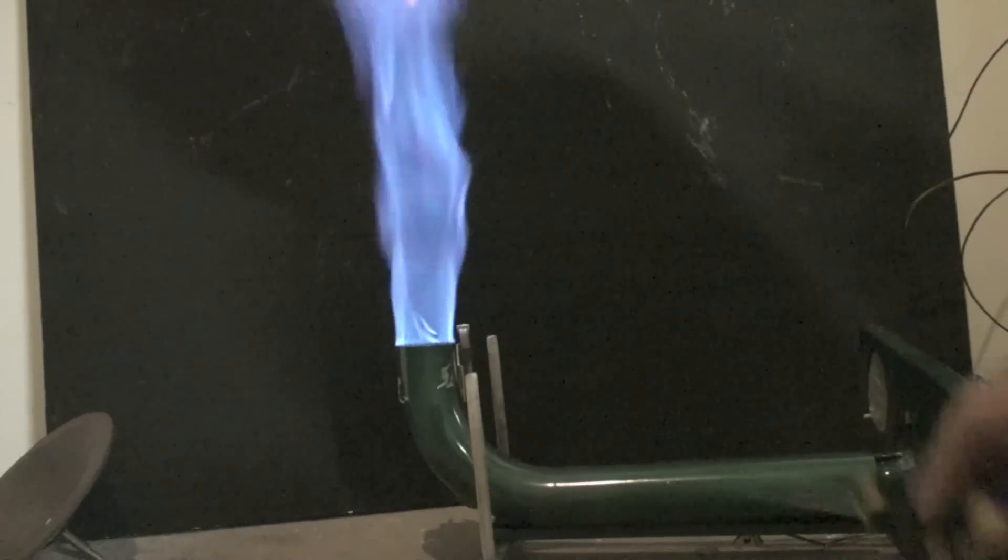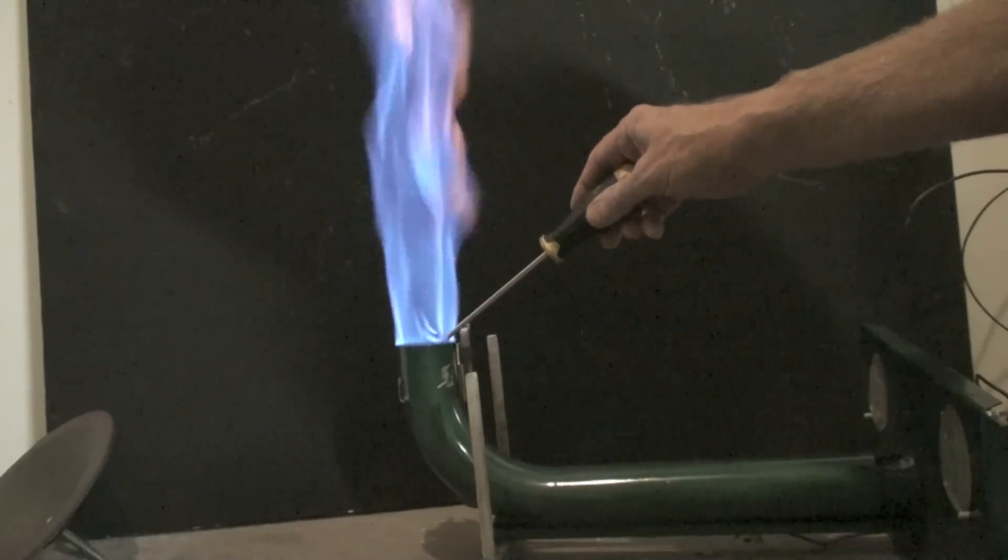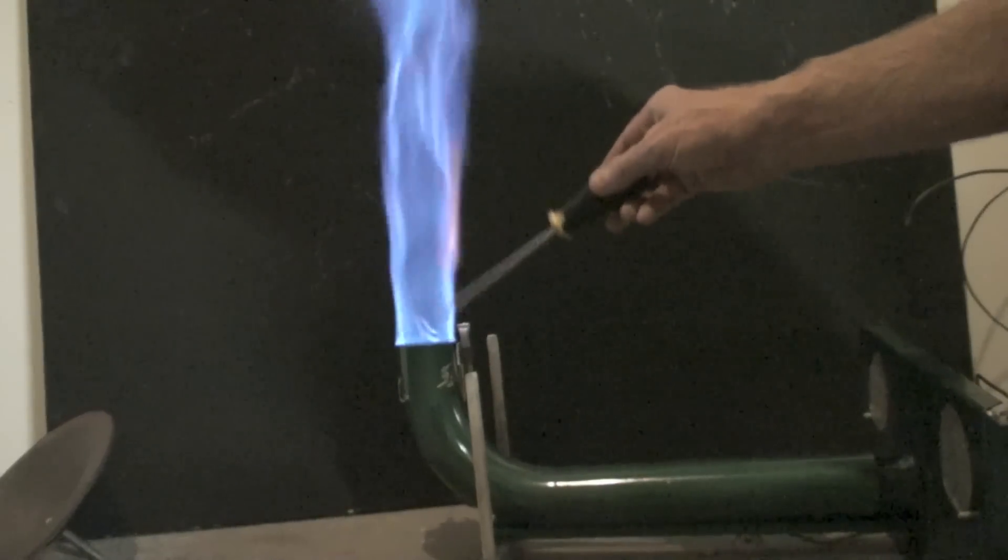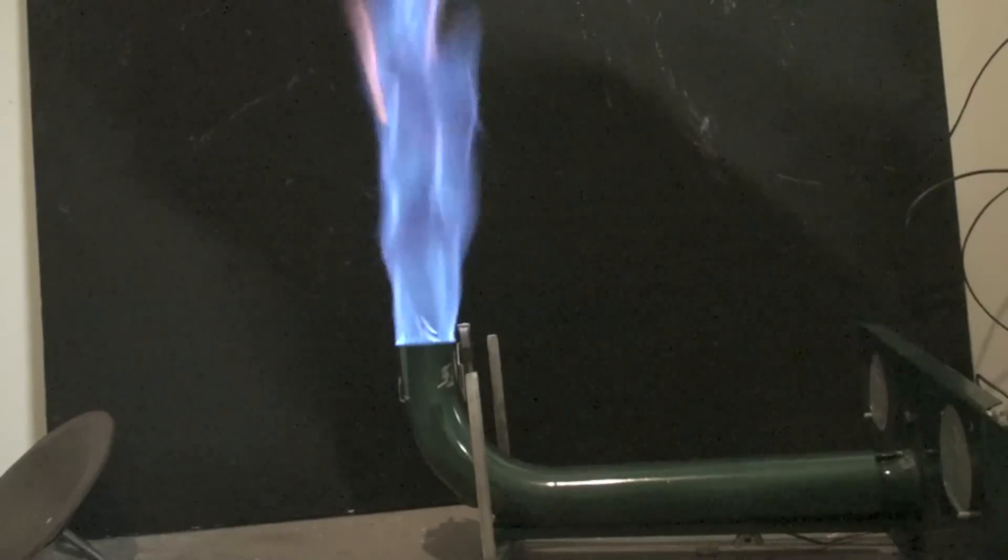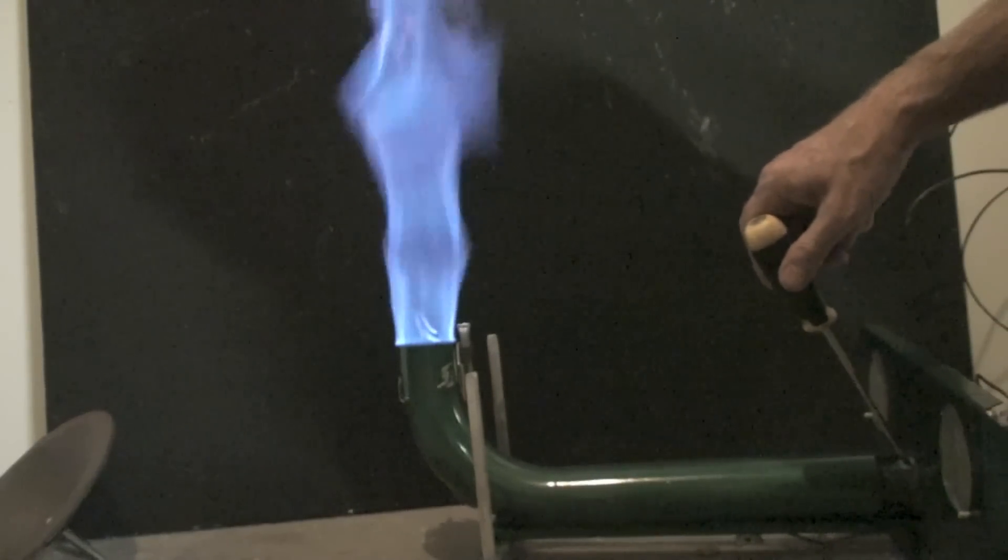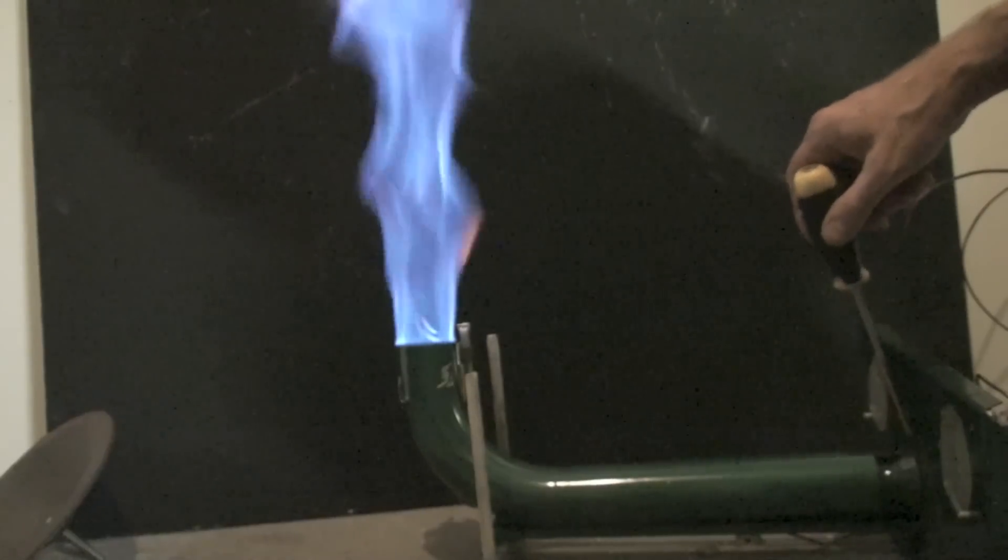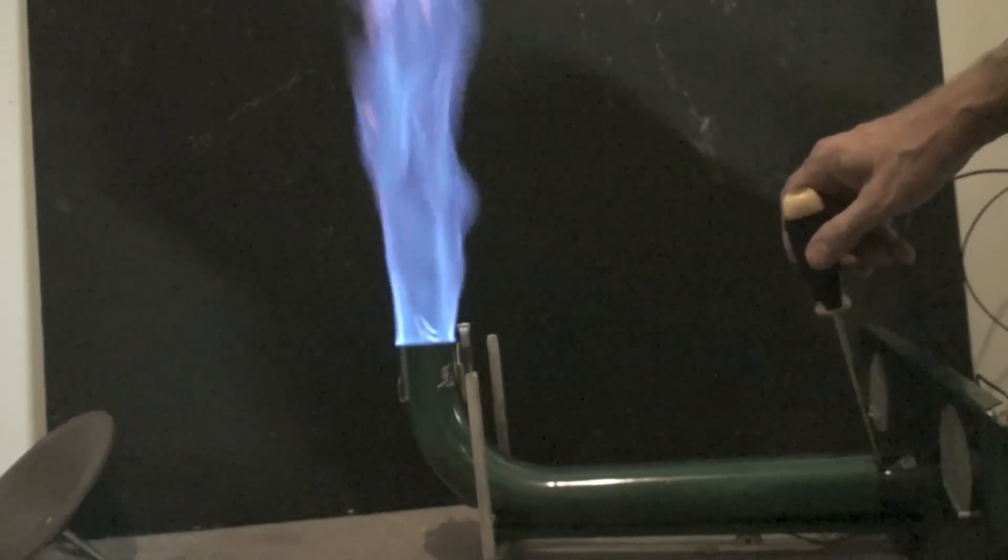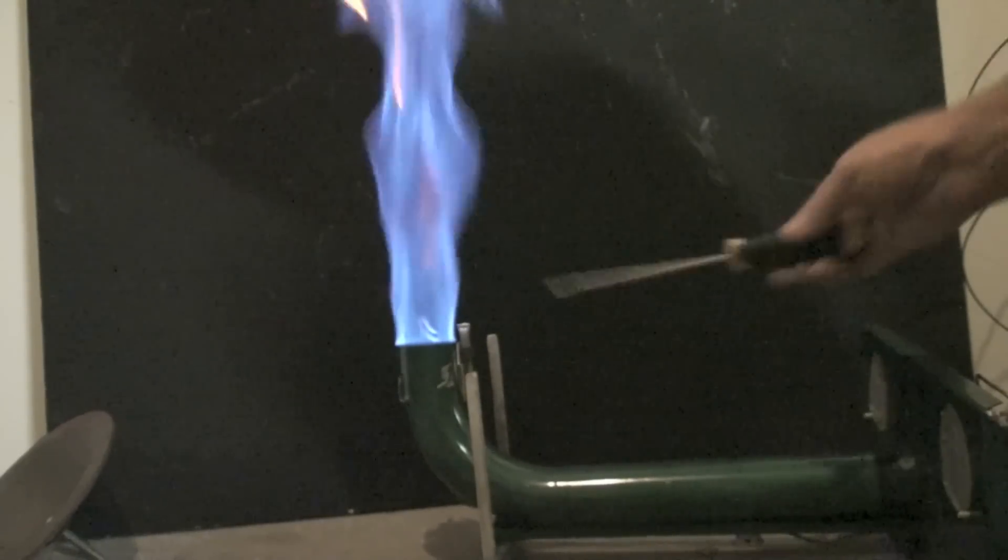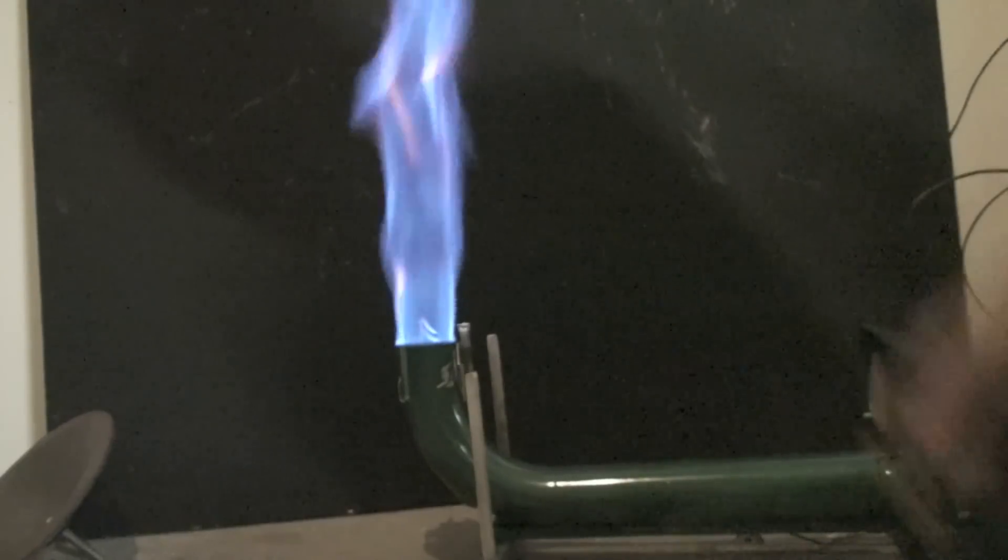Remember, the primary air is the air that's coming in with the gas, right there. There's an orifice in here, and it draws primary air in through here, and up to here, and secondary air completes the burn.